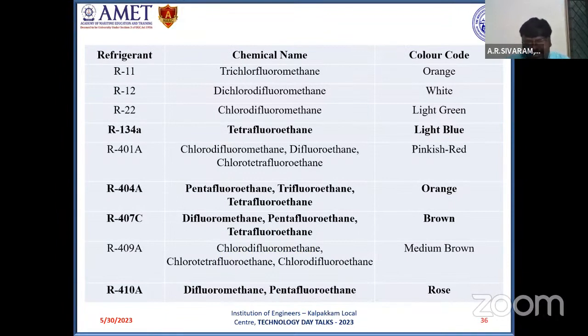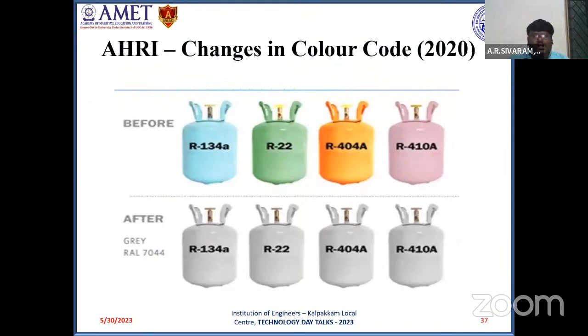And I have highlighted the color code for a few important refrigerants. R134A, the color code is light blue. R404A, which is used in marine refrigeration systems on a large scale, is orange in color. R407C is brown. R410A, which is used in domestic air conditioning systems on a large scale, the color code for it is rose color. Changes in color code.